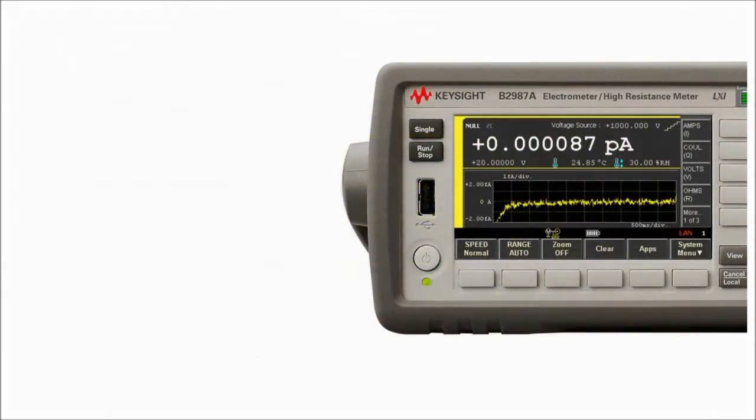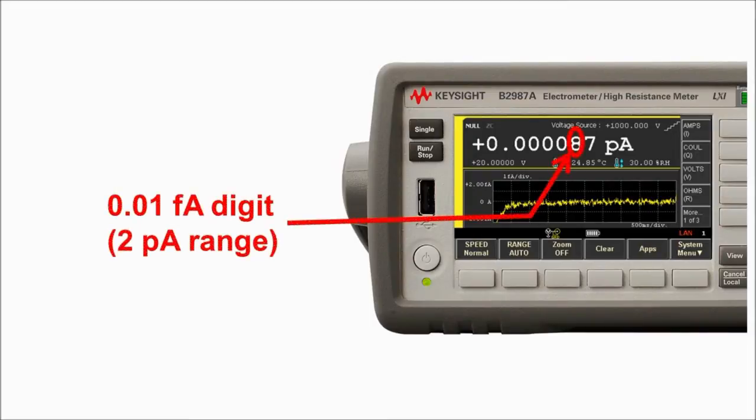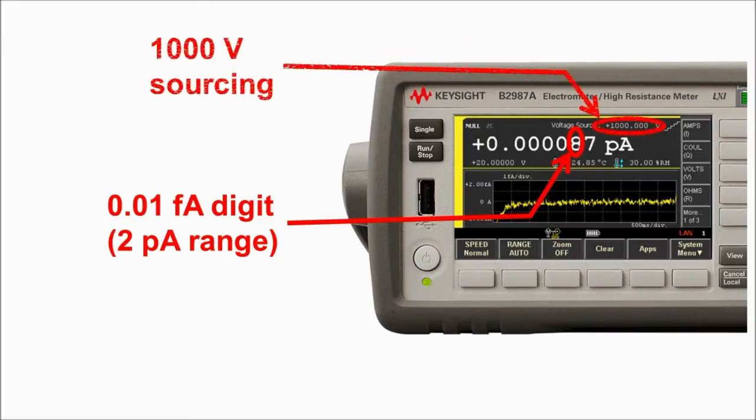Each instrument has a 2 picoamp current measurement range with 0.01 femtoamp minimum resolution. In addition, the electrometers allow up to 10 peta-ohms resistance measurements using a built-in 1000 volt voltage source.